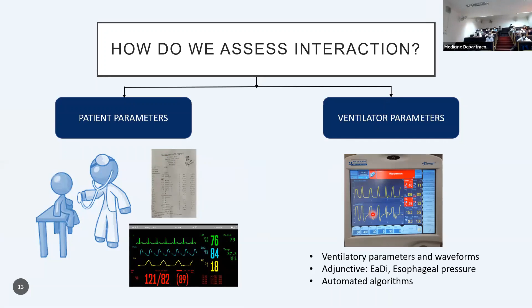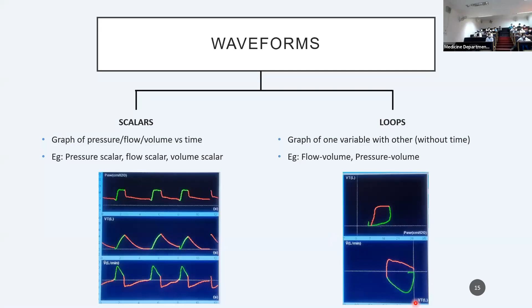If we need to understand ventilator management and understand the asynchronies, first of all, we need to understand the waveform graphics. So what are the waveform graphics in mechanical ventilation? There are broadly two types, scalars and loops. Scalars are graphs of these variables against time. So we have a pressure scalar, in which we plot pressure against time, a volume scalar, Vt, tidal volume against time, and a flow scalar, V dot, against time. The other type is loops. Loops are the graph of one variable against another without time. So we have the pressure volume loop, where pressure is plotted against volume, and the flow volume loop, in which flow V dot is plotted against volume Vt.